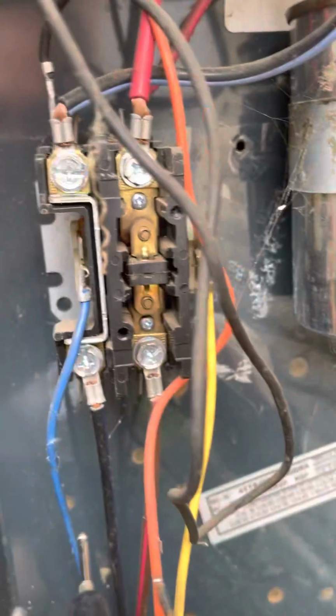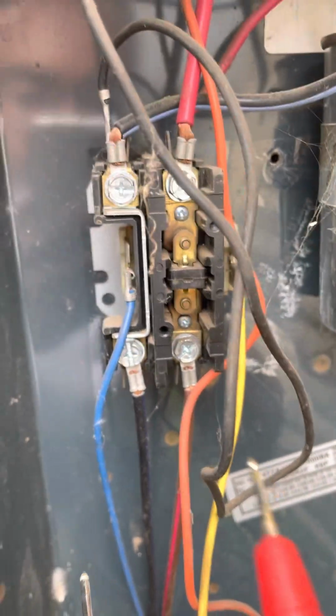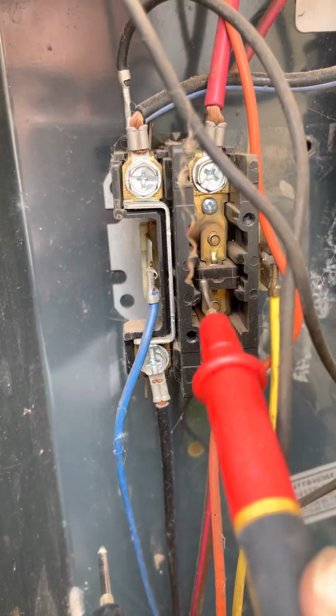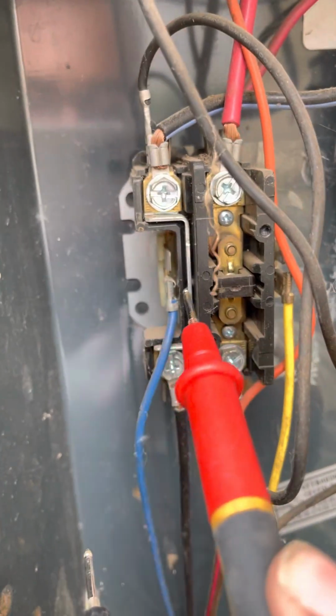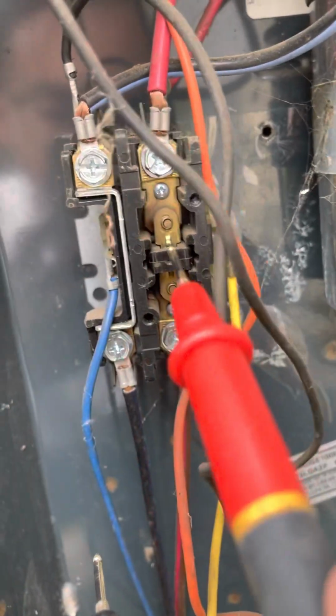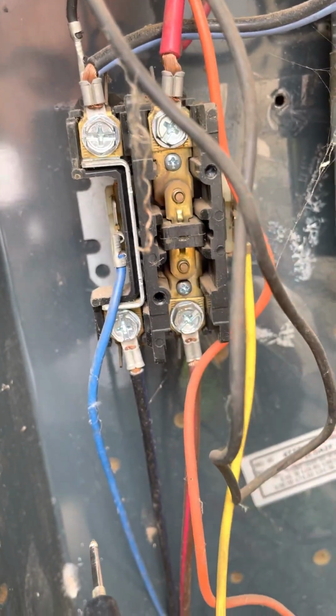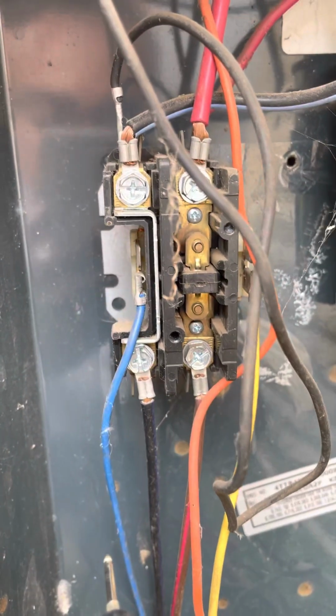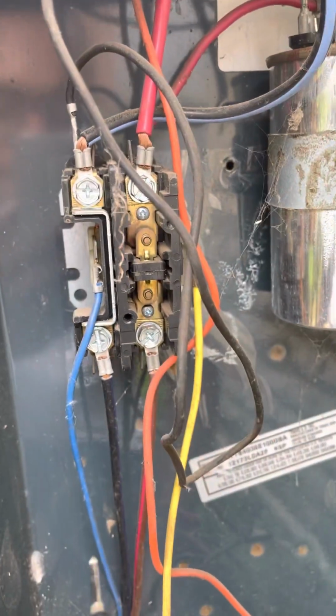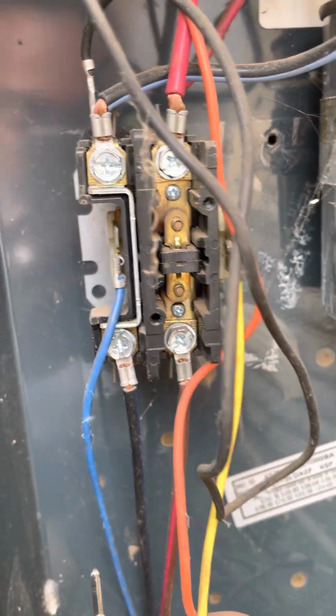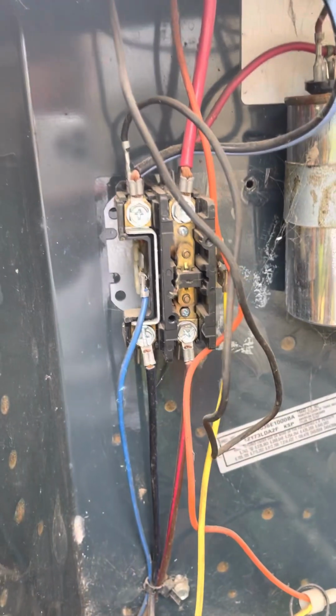I don't know if you can hear that buzzing, but that comes from this contactor. The contactor is pulled in, and that's because we have 24 volts on the coil of the contactor. The 24 volts comes from inside your indoor air handling unit, from the transformer. And we can actually see that we have 24 volts on this contactor coil. I can do that here.